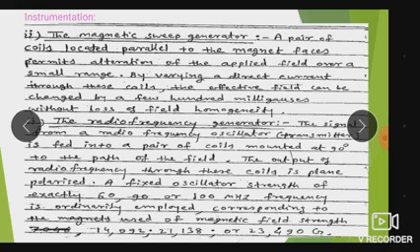Next, the radio frequency generator. The signal from a radio frequency oscillator transmitter is fed into a pair of coils mounted at 90 degrees to the path of the field. The output of the radio frequency through these coils is plane polarized.